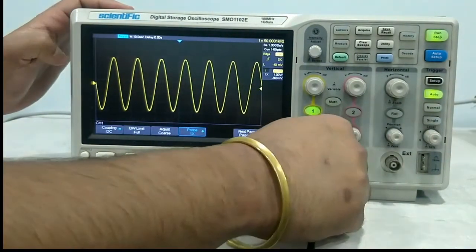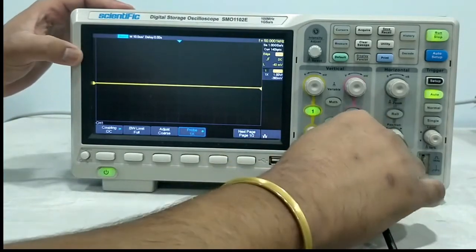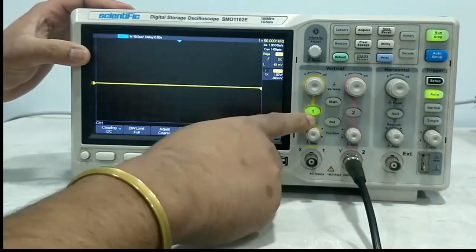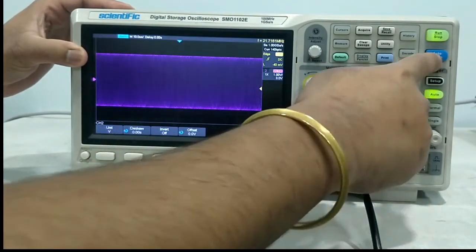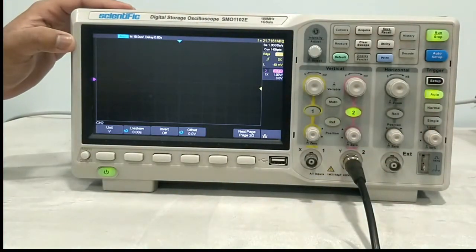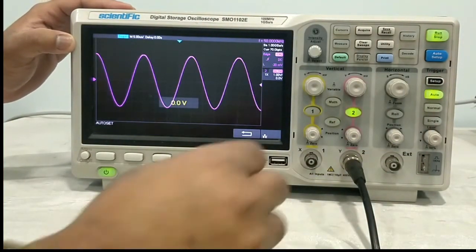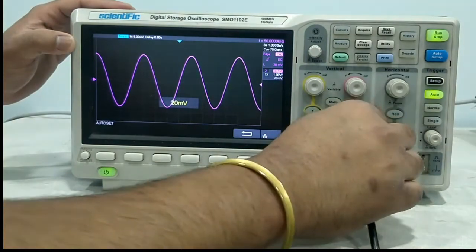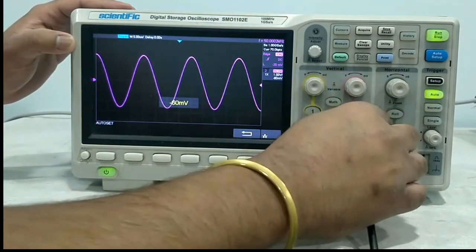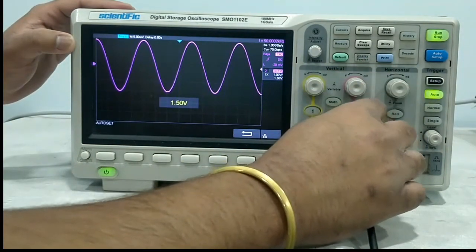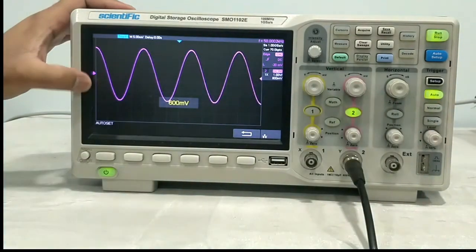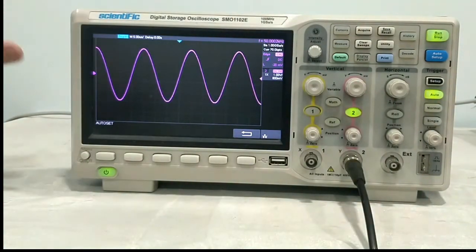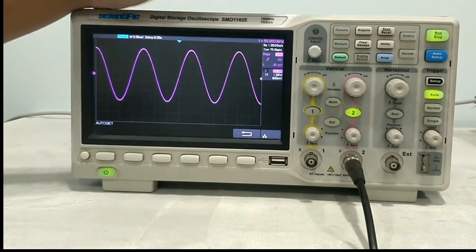The same signal, if I apply to channel 2 — we will turn off channel 1 and enable channel 2. This is auto setup. Now you can see the same signal: this is also 5 boxes, 1 volt per division, so 5 volt, 50 kilohertz signal.